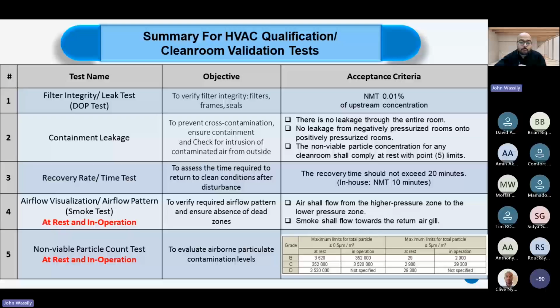So it's important for you to know that by having a higher cleanliness grade, I will also be having a high pressure inside this room and this grade. And the air is expected to be flowing from the highest pressure to the lowest pressure, or from the highest cleanliness grade to the lowest cleanliness grade. Also, this test should be performed at rest and in operation in order to make sure what is the impact of any movements or any operating personnel inside the room, how they might impact the airflow inside this room.